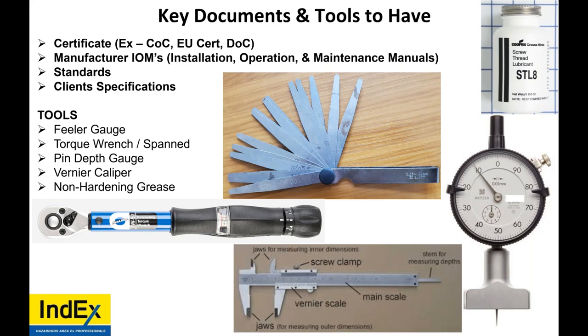If it's explosion proof, that's a different story. But if you're using flameproof and explosion proof on site, you are at significant safety risk. Okay? Do not drill flameproof enclosures. We drill cable gland for explosion proof on site. Now, explosion proof? Yes, but we want to not confuse people. Once again, only explosion proof, and you must do as the manufacturer's certificate, their listing indicates, what their IOM states. Speak to the manufacturer, double check, have the proper drilling facilities. It's a dangerous thing if you don't do it correctly.